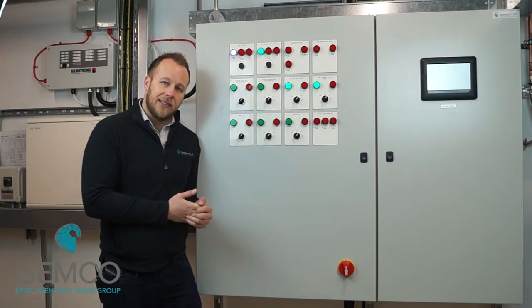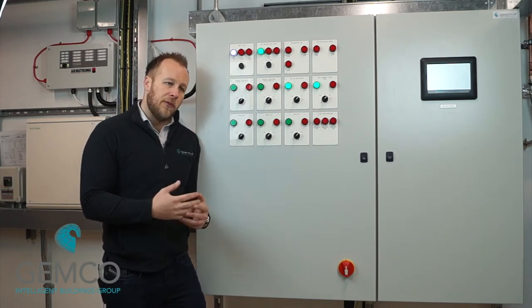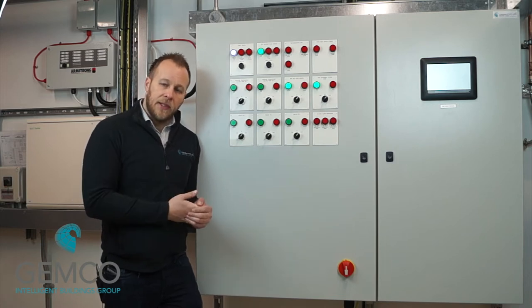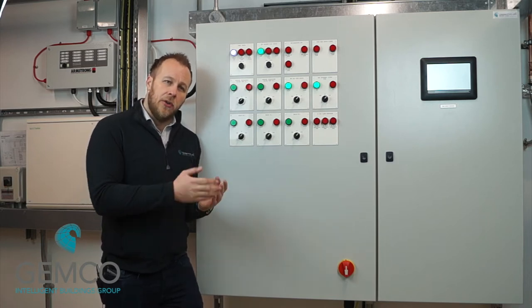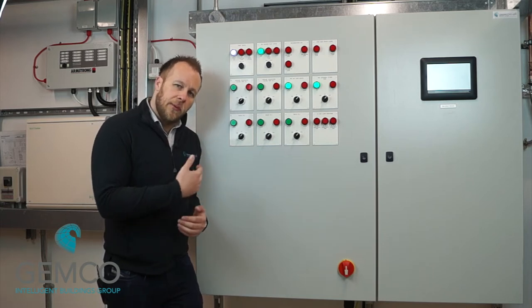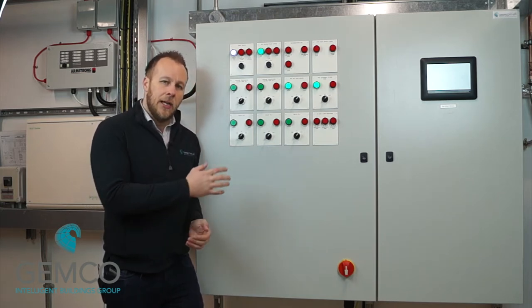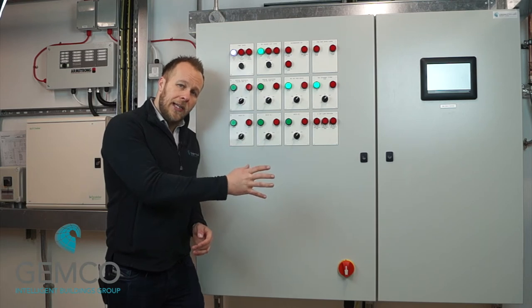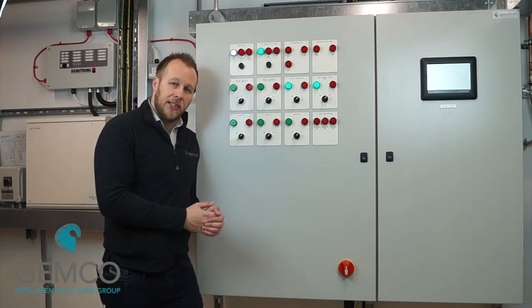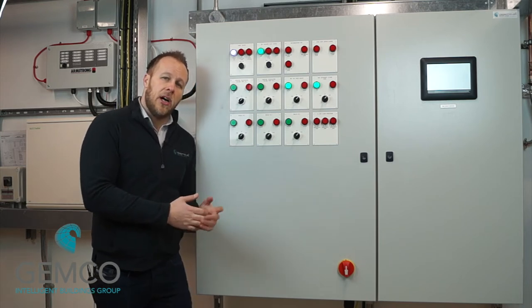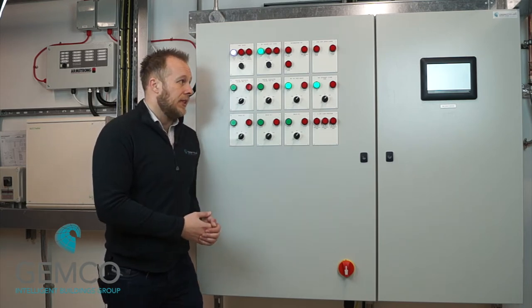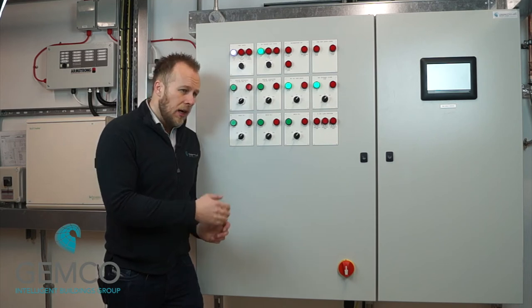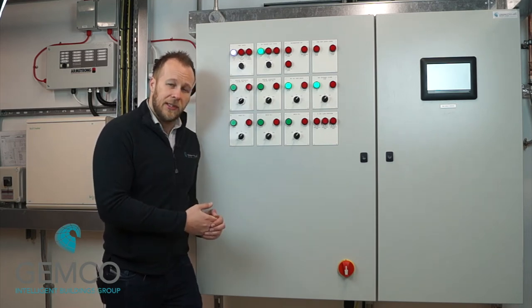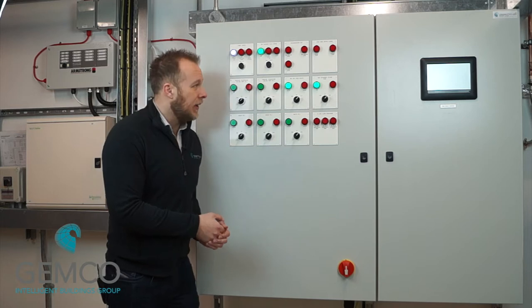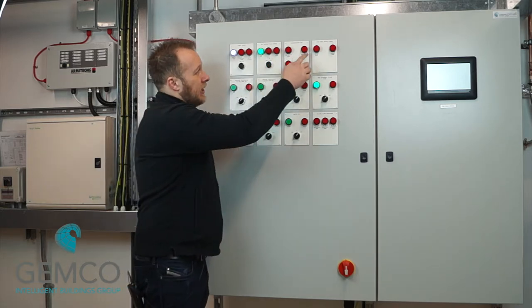If you've got a leak somewhere, or radiators come off the wall, or you've got a pump that's got a leak, the last thing we want to do, once that pressure drops, is continue to run the pump. So this panel will monitor only the pressurization unit, it has no control over it, but if it goes into high or low pressure, then it will shut the pumps down and the boilers as well. Last thing we want, if there's no water in the system, is to run the boilers. Okay, so that's the pressurization unit.